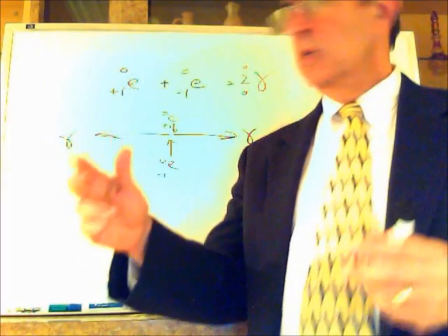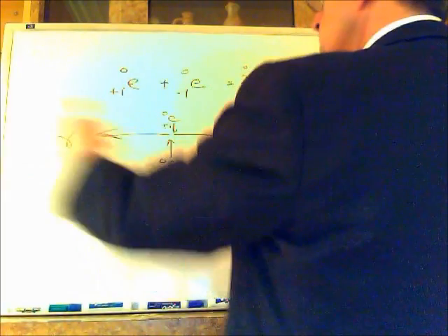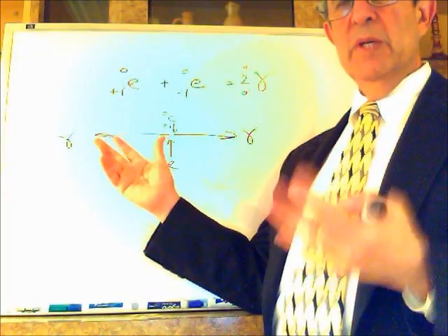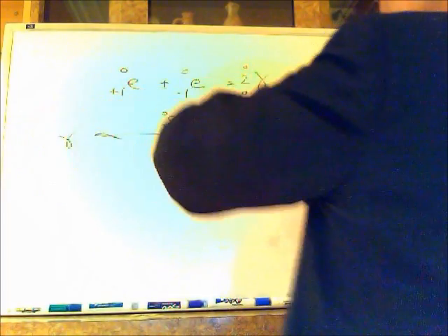You can always tell when this is happening if you have the right kind of detector, because you can set a detector up in such a way that it does what's known as coincidence counting. And you can actually see simultaneously that you will detect 2 gammas that are really 180 degrees apart. So wherever they happen to be, this is the way that positron emission tomography, which we'll talk about later on, actually works, because it's producing these gammas, and these gammas are going to be produced in pairs in various directions, but they'll always be 180 degrees apart from one another. So if there's an extraneous gamma that doesn't have that 180 degree counterpart, it's not included as part of the count. It's only when the detector senses both of those gammas simultaneously that you know that that's an annihilation event. And that's what happens during positron emission tomography.